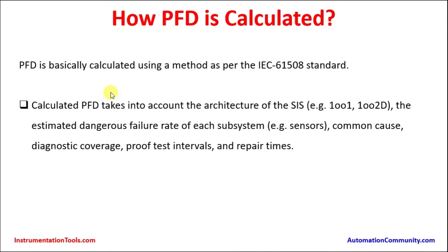How is PFD calculated? PFD is calculated using a method as per IEC 61508 standard. The calculated PFD takes into account the architecture of the SIS — safety instrumented system — such as 1oo1, 1oo2D, 1oo2, 2oo3, etc. It also considers the estimated dangerous failure rate of each subsystem, sensors, common cause, diagnostic coverage, proof test intervals, and repair times of the sensors, logic solvers, and final elements.